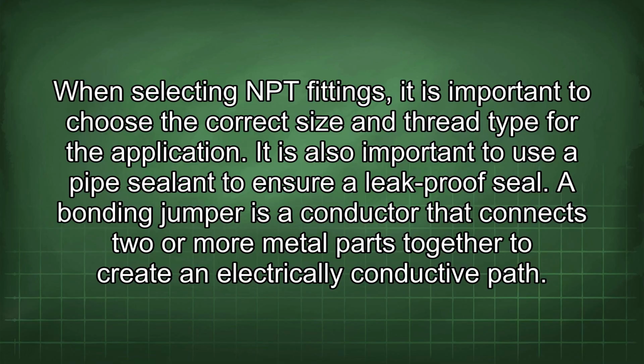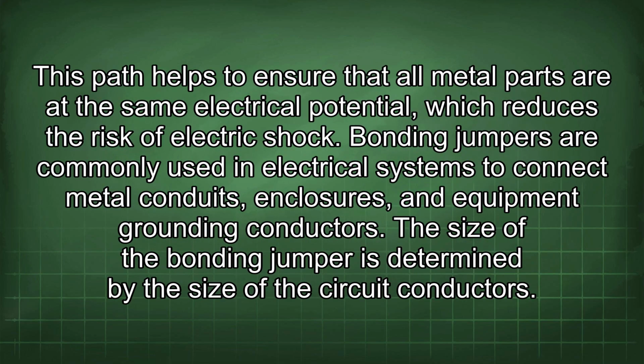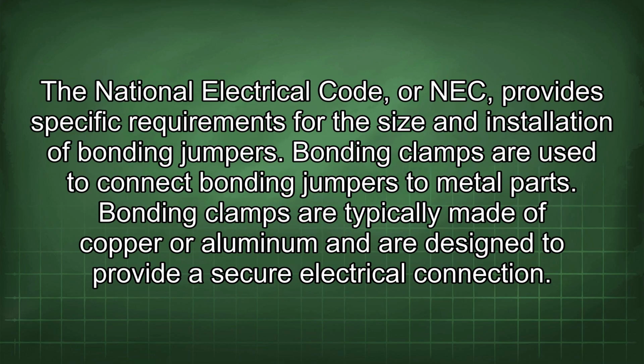A bonding jumper is a conductor that connects two or more metal parts together to create an electrically conductive path. This path helps to ensure that all metal parts are at the same electrical potential, which reduces the risk of electric shock. Bonding jumpers are commonly used in electrical systems to connect metal conduits, enclosures, and equipment grounding conductors. The size of the bonding jumper is determined by the size of the circuit conductors. The National Electrical Code, or NEC, provides specific requirements for the size and installation of bonding jumpers.